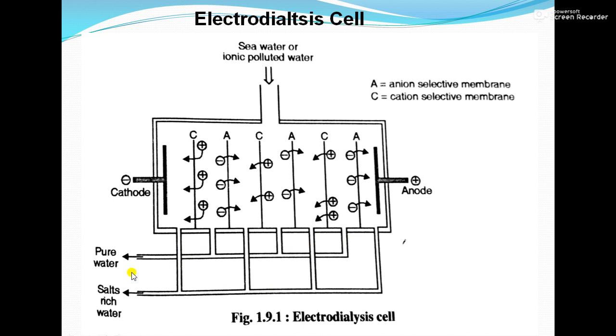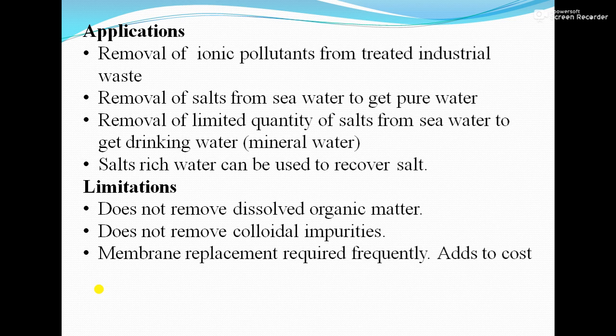If NaCl is present, you can recover NaCl from the salt-rich water. Applications: removal of ionic pollutants from treated industrial waste; removal of salt from seawater to get pure water; removal of limited quantities of salt from seawater to get drinking water; and salt-rich water can be used to recover salt. Limitations: it does not remove dissolved organic matter, it does not remove colloidal impurities, and membrane replacement is required frequently, which increases the cost of the process.